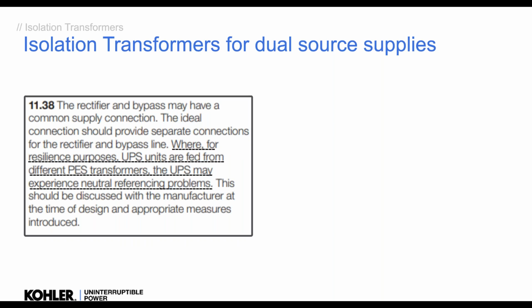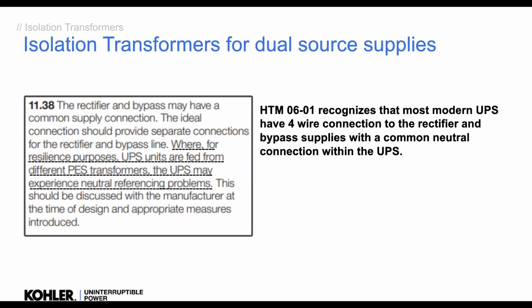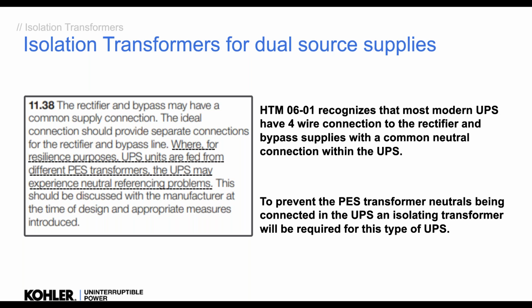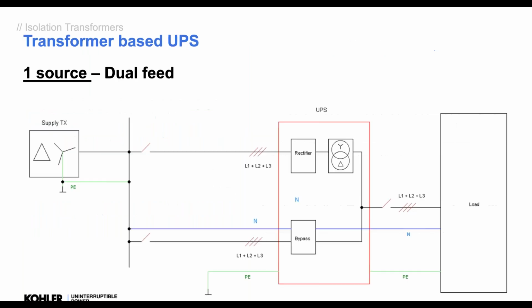Because it does say, where for resilience purposes, UPSs are fed from different PES transformers, the UPS may experience a neutral referencing problem. Okay? So it recognizes that modern UPSs have a four-wire connection on a rectifier and a four-wire connection on bypass. Older UPSs, let's say 20 years ago, would have a three-wire rectifier and a four-wire bypass, different, okay? So when we have a four-wire rectifier and four-wire bypass, if we were to connect that from two different transformers, we would be connecting the neutral together, and that would not be good, so therefore we need a transformer to isolate.